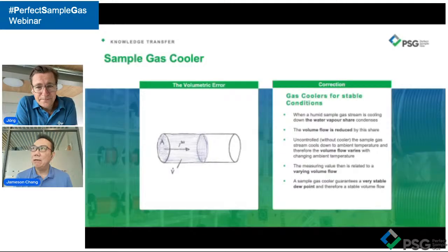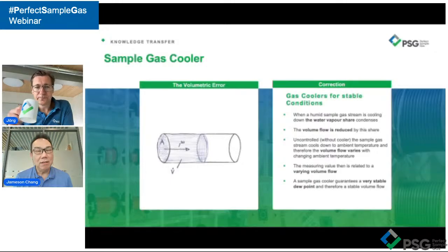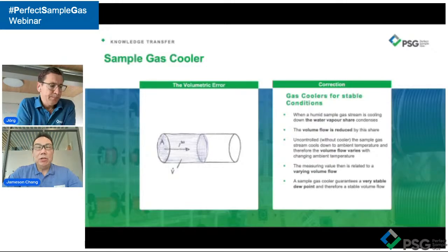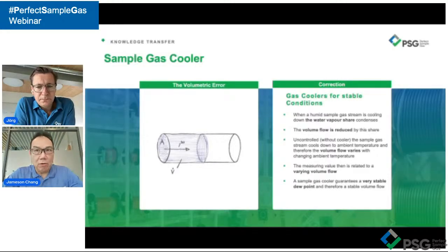So you see, a most common issue which I watch with system integrators is the connection between the heated sample line and the gas cooler. Bear in mind that gas is different from water. Condensation of water can easily take place, because the ability of the gas to hold the temperature is rather weak. Therefore, many times I saw that the heated line, when it enters the analyzer cabinet, has a length of unheated sample PTFE tube that goes into the gas cooler, as much as 1 meter.